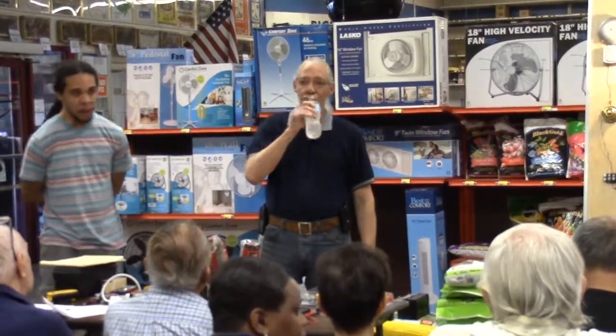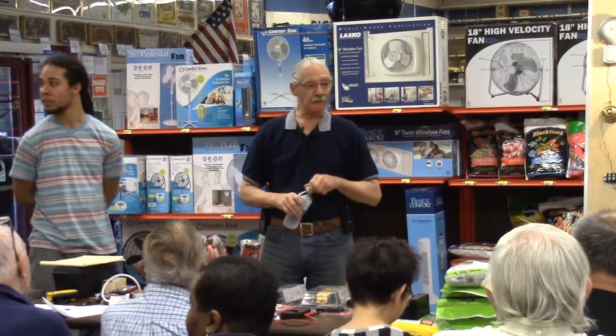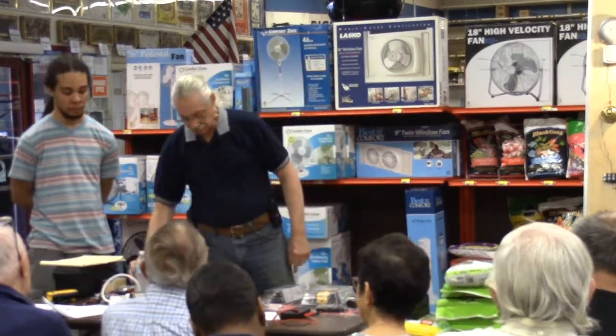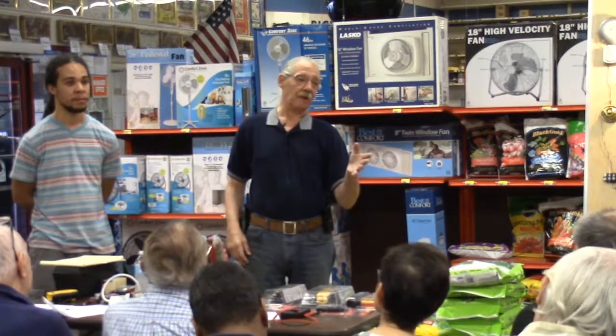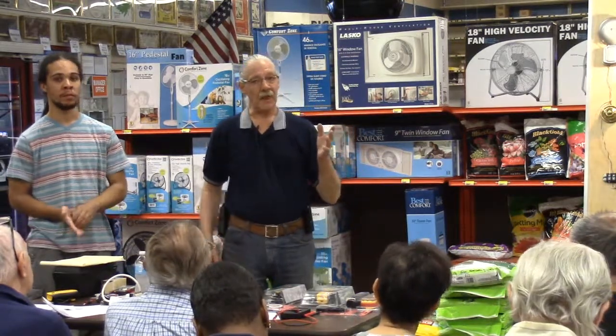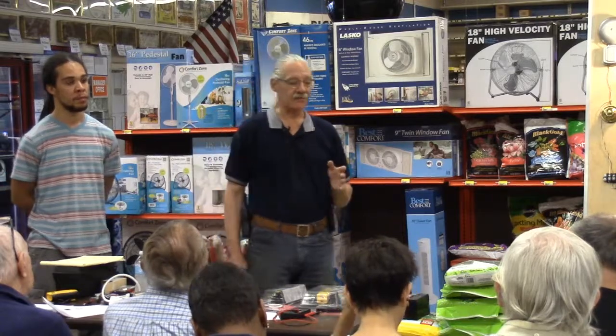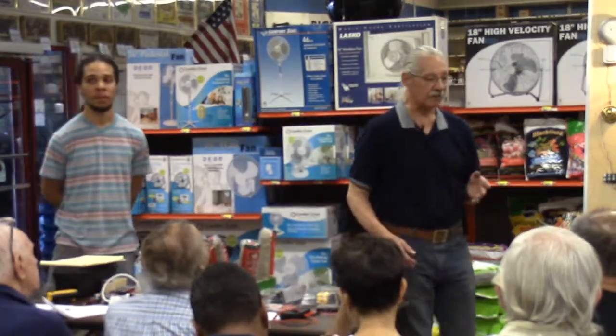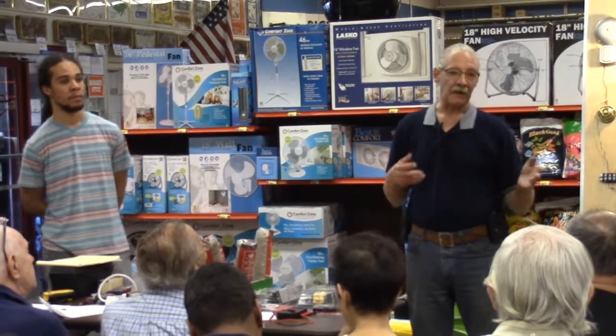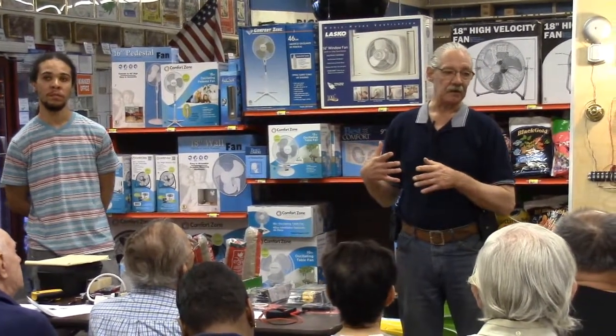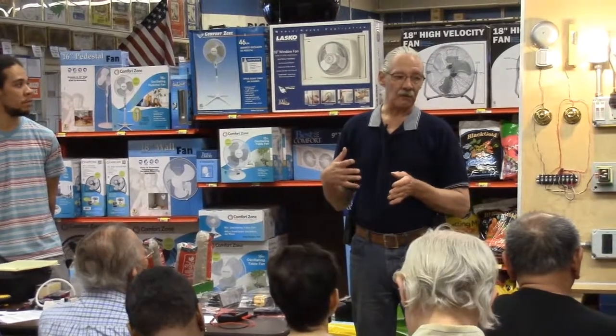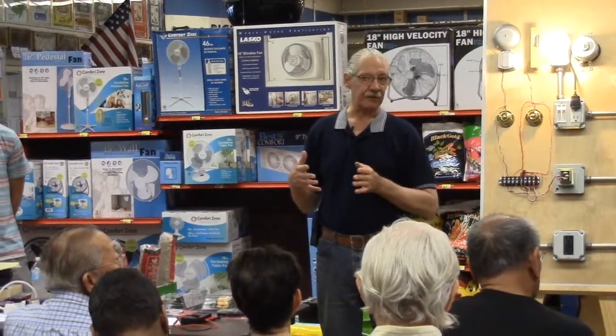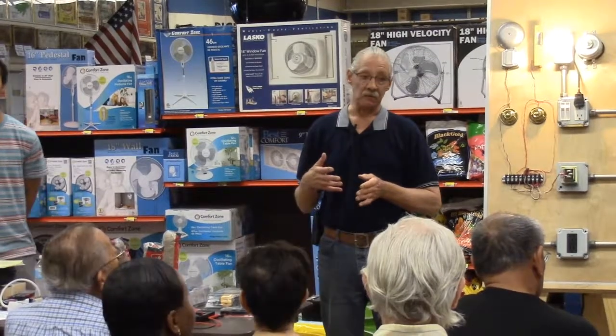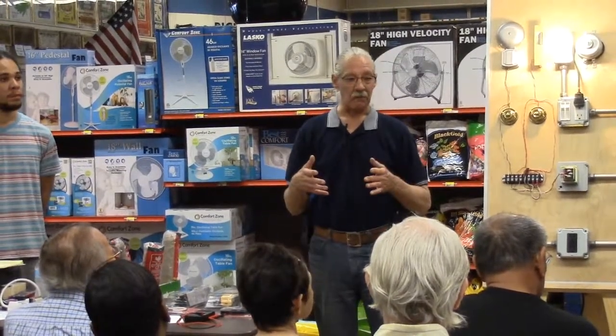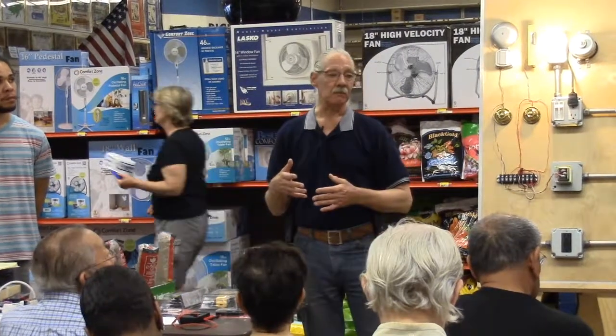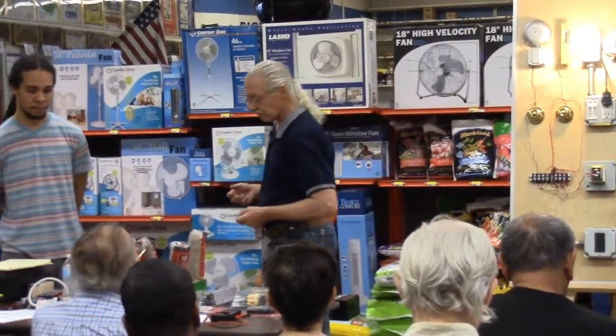Can it shock you? No. But you don't know that until you test it, because that could also be indicative of somebody who wired a circuit in series as opposed to parallel, and half the voltage is being eaten up by something else. So if there were two things on a 120 volt circuit and you're getting 60 volts, yes, that can shock you if it was a series problem and not an induced voltage problem. So you still have to be careful.